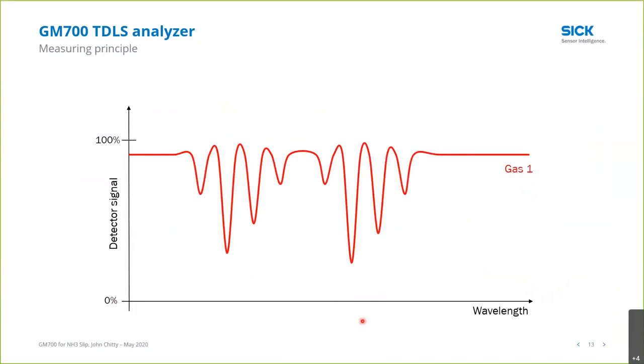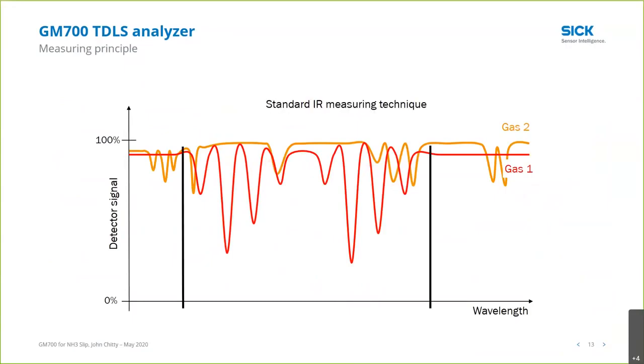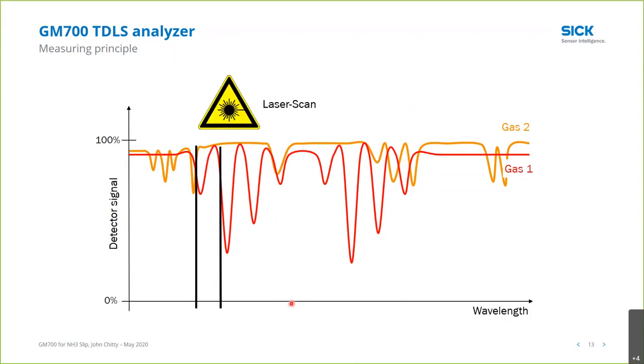More about the technology. If you can imagine this as being the infrared spectra, one gas has absorption peaks in these areas. You add a second gas or a background gas to that, and you have other absorption peaks, and some of them are on top of each other. In the infrared range, when we use an infrared analyzer, we're measuring this entire or a good part of the spectra. Even though we use wavelength filters, it's still a pretty wide band. With TDL, with lasers, we're able to narrow that band down to a much smaller area and only look at the peak that we're interested in. So that's what we mean by high spectral resolution. We're only looking at one peak in the spectrum.